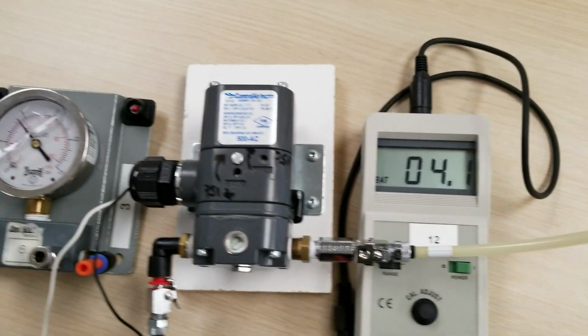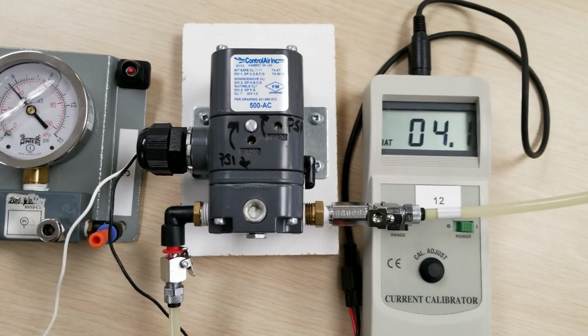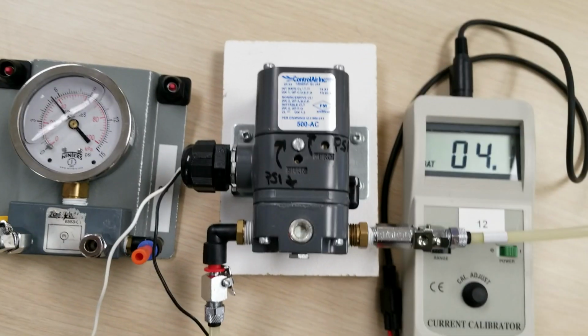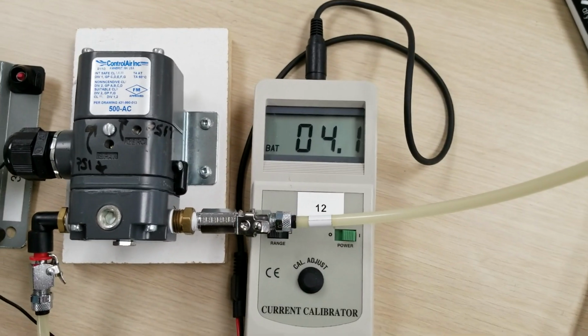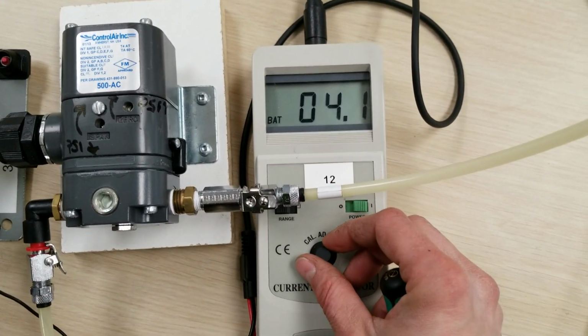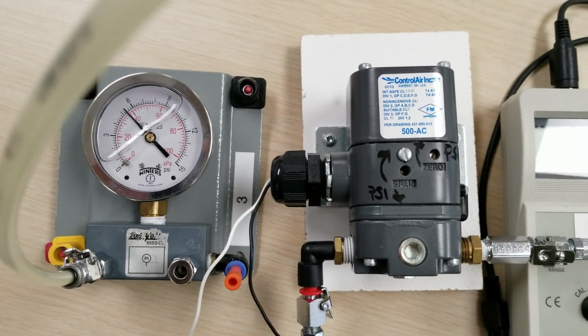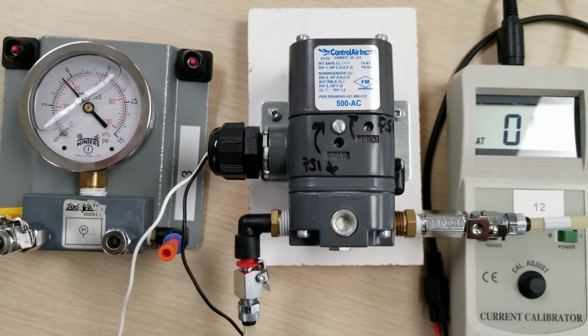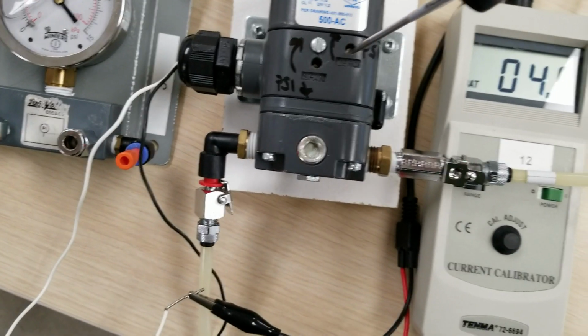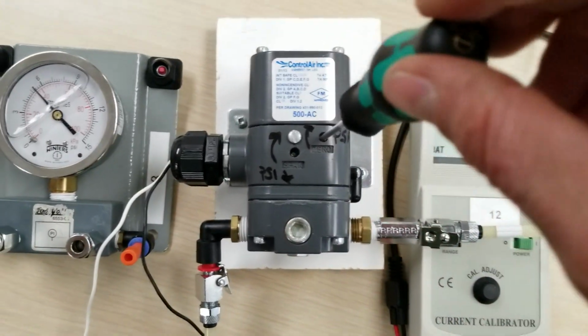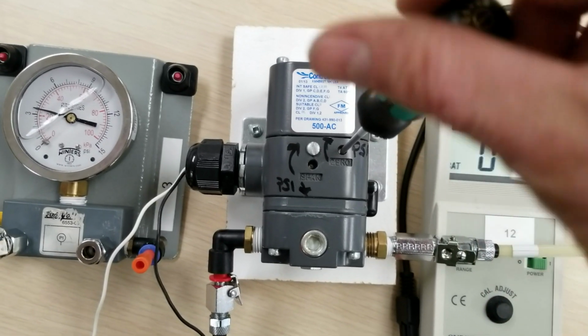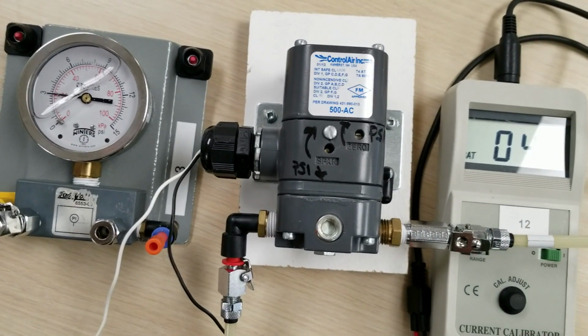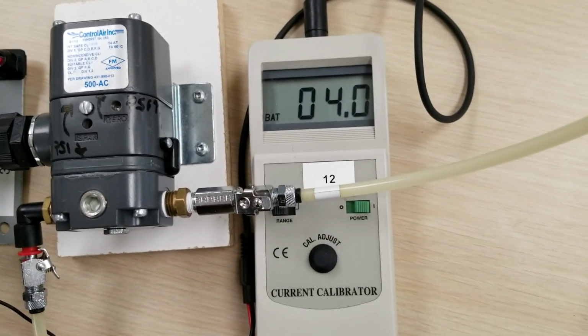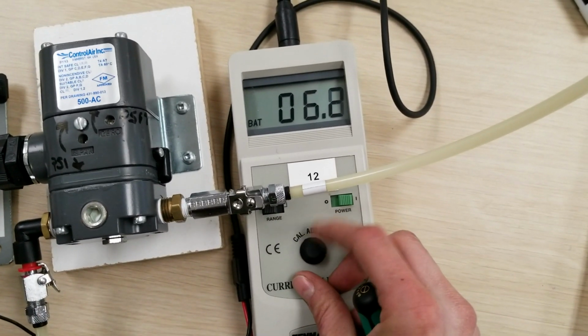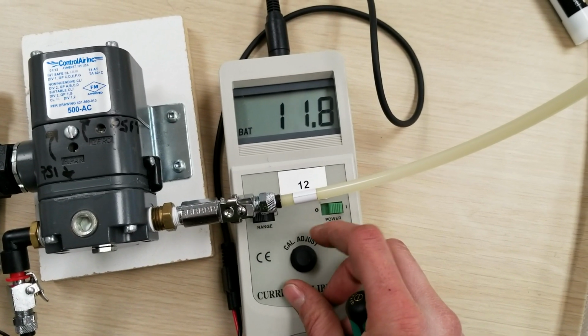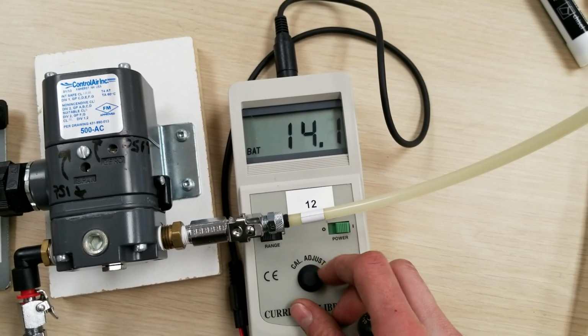So here we come to our transducer, and we want to calibrate our transducer so that we get 3 to 15 psi on a 4 to 20 milliamp signal. I can see here I have 4 milliamps, and I do not have the desired pressure at 4 milliamps. So I start with my zero adjustment, and I start bringing it down so that at 4 milliamps I have 3 psi. Now I will adjust it up to my 20 milliamp signal.